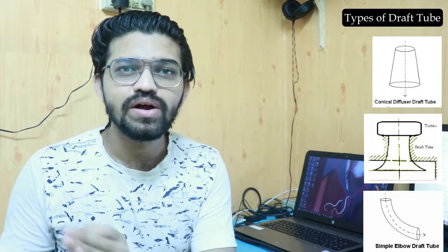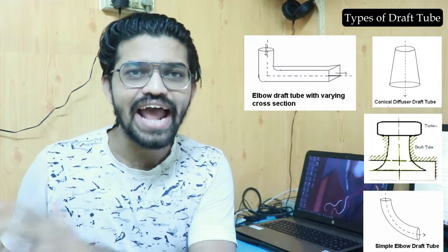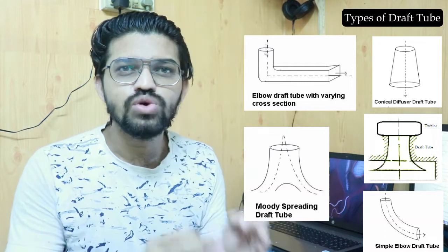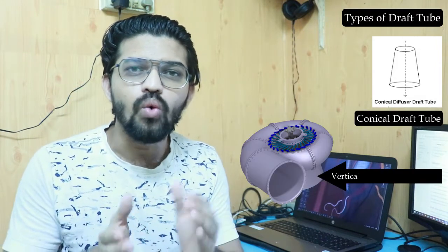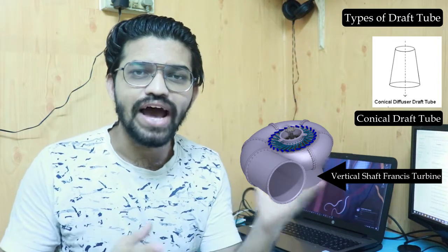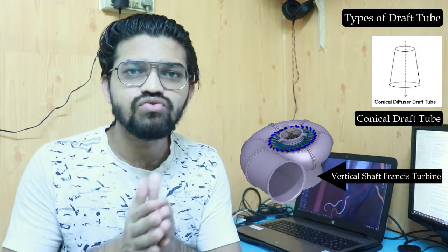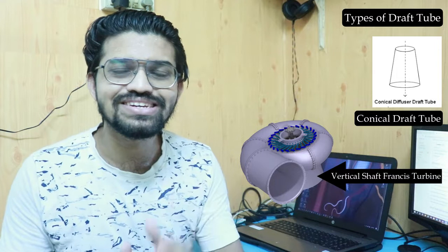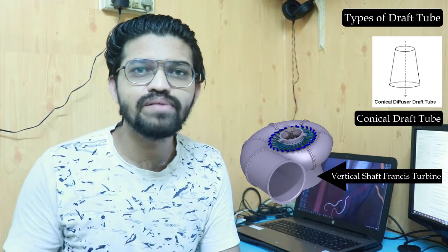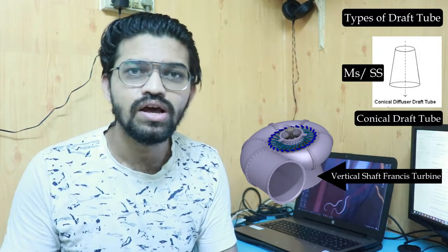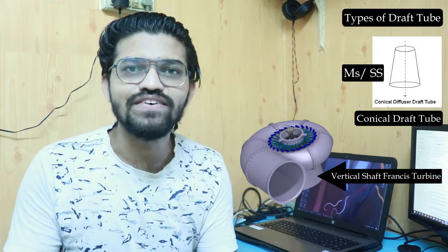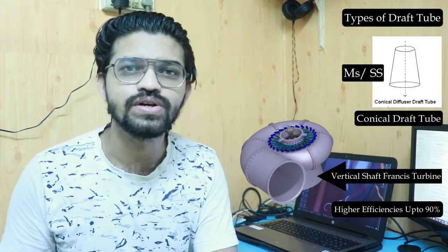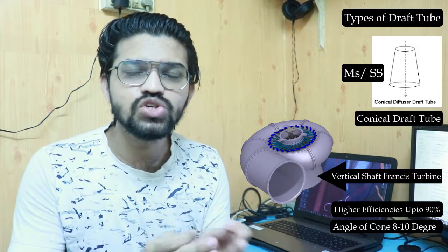There are mainly five types of draft tube. The first is the conical draft tube, which is mostly suitable for vertical shaft Francis turbines. As seen in the previous example, it is shaped like a frustum of a cone. It can be made of mild steel (MS) or in certain scenarios stainless steel. This type of draft tube has a very high efficiency of around 90%. The angle of the cone is limited to between 8 and 10 degrees.